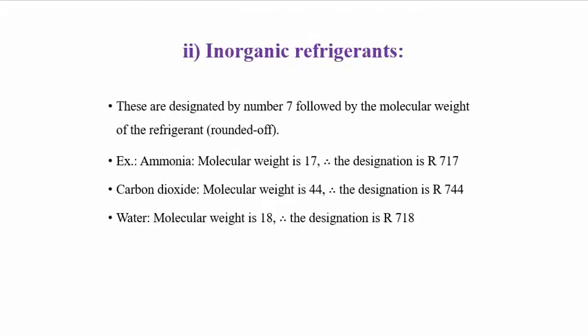The chemical formula for R22 is CHClF2. Similarly, R12 is CCl2F2 and from the derivative of ethane we have R134a that is C2H2F4. For inorganic refrigerants, these are designated by the number 7 followed by the molecular weight. For example, ammonia has molecular weight 17 and is designated R717; carbon dioxide has molecular weight 44 and is designated R744; water has molecular weight 18 and is designated R718.